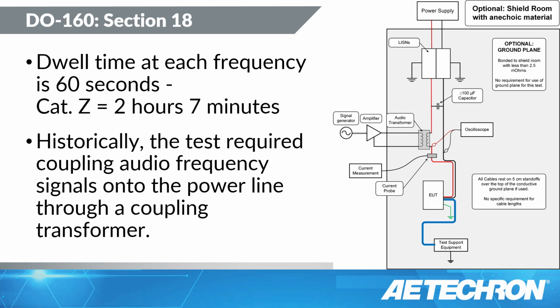However, with these 60-second dwells, if you're performing the test, say, to category Z, which has 127 frequencies that you have to test from one end to the other, that's 2 hours and 7 minutes of test time. So this test is going to be a slow test. It's going to take you a while to perform.